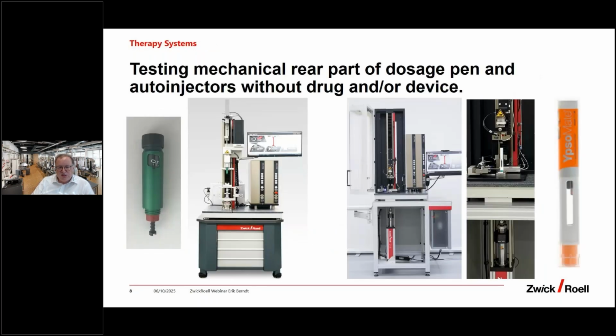What are some trends, some news in this area that I'm facing? Perhaps the most interesting is looking at the standard. We are testing a full product, the device with the drug, and the procedure is quite clear on what to be tested. But there's a big trend toward testing the mechanical part of these devices, of a pen, of an autoinjector, without a drug inside.